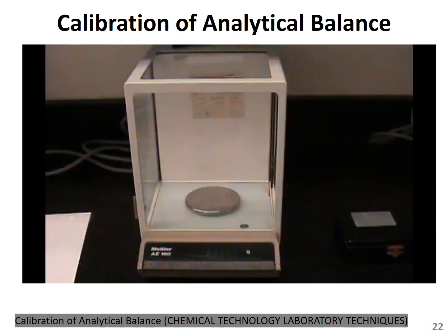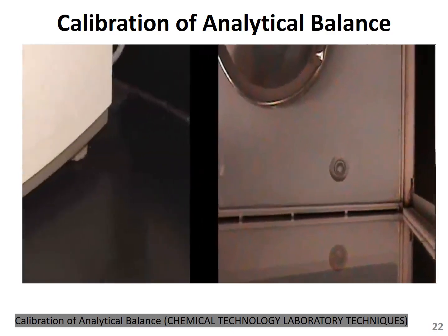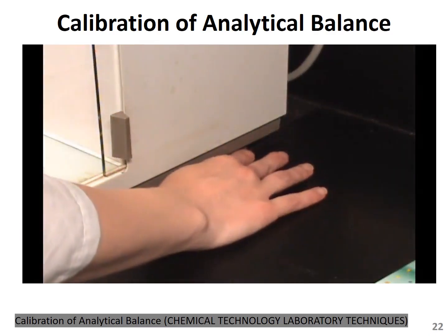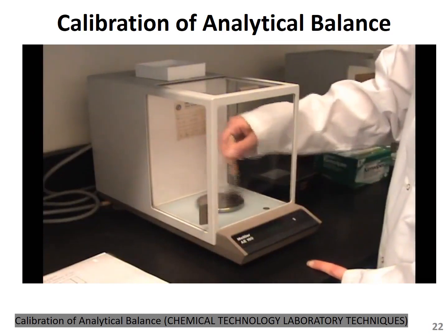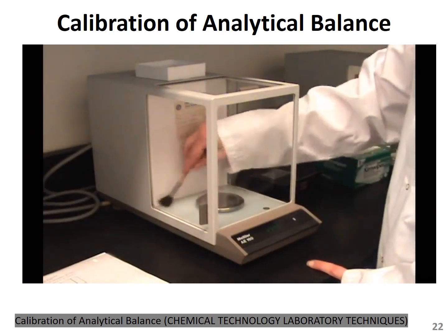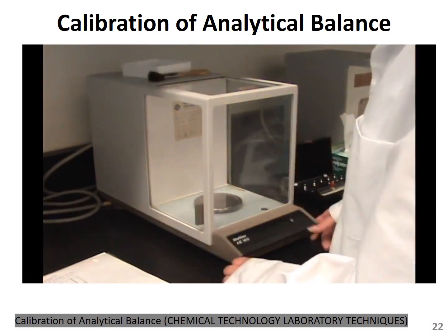The analytical balance is a precision instrument used for weighing masses to 4 decimal places. The balance must be leveled to assure repeatable results. Locate the air bubble on the balance. The leveling feet are at the back of the balance housing. Turn these until the air bubble is in the center of the level control. Balances need to be clean at all times. Take a soft bristled brush and sweep off the balance tray and surrounding area. Make sure all the balance doors are closed.